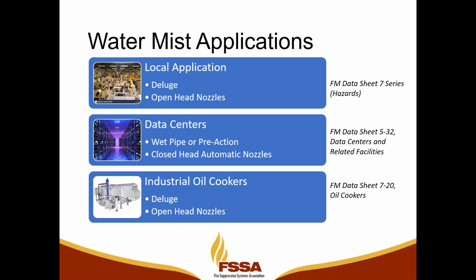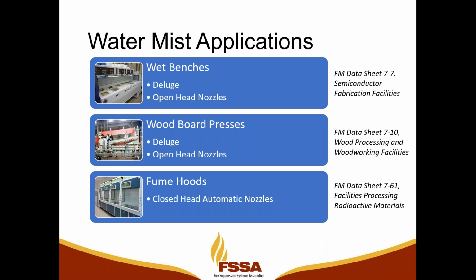And when we test our systems to the FM protocol, FM's going to make sure that our nozzles and our nozzle arrangement are not going to splash oil all over the place. So water mist is ideal for industrial oil cookers as well. Next slide. Then we've got the final three FM predefined testing protocols and approvals, and these are kind of the niche applications. You have a few water mist manufacturers that have gotten approvals for one or more of these niche applications. And I won't go into great detail here because I see we're at the 48-minute mark.